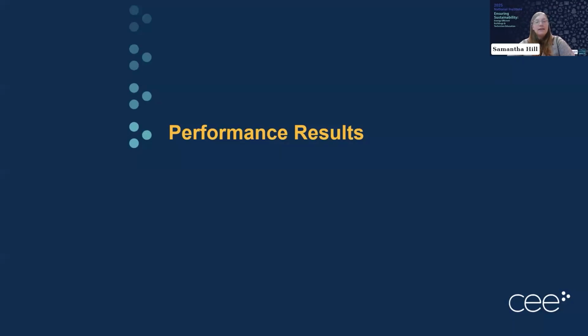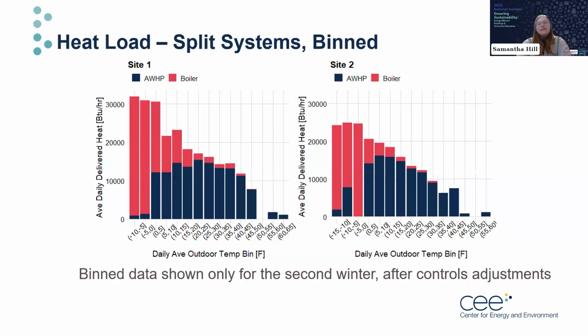What did they perform like? Here are our two split system homes, and these plots are showing how much load was delivered on average per day as a function of outdoor air temperature, where the blue bars indicate how much load was delivered by the heat pump, and the red indicates how much was delivered by the backup boiler. In both cases, the majority of the heating load for the whole heating season was provided by the air-to-water heat pump, and the boiler was primarily serving the heating load during the coldest part of the year, below 0 degrees Fahrenheit.